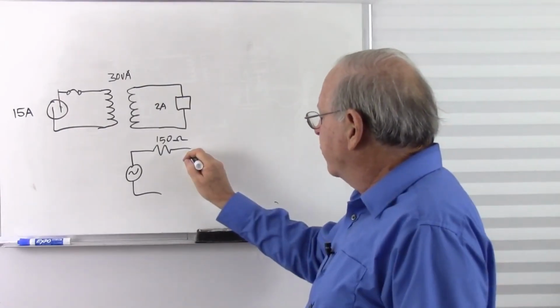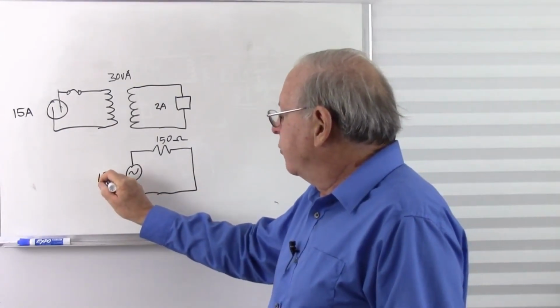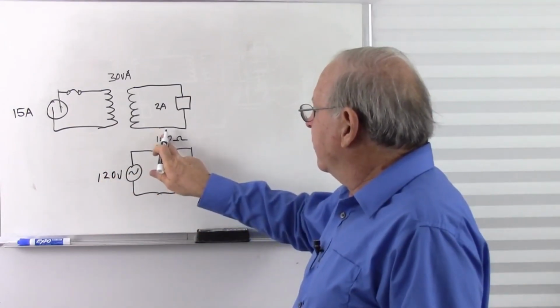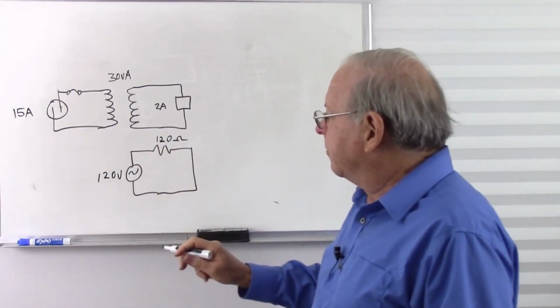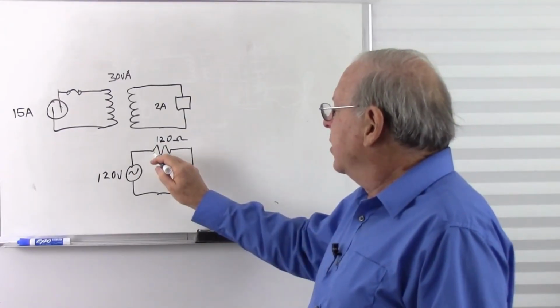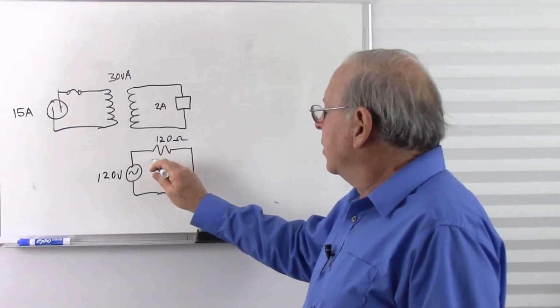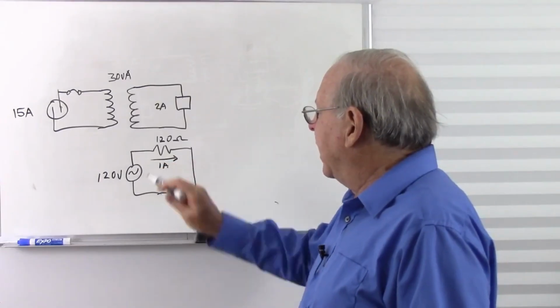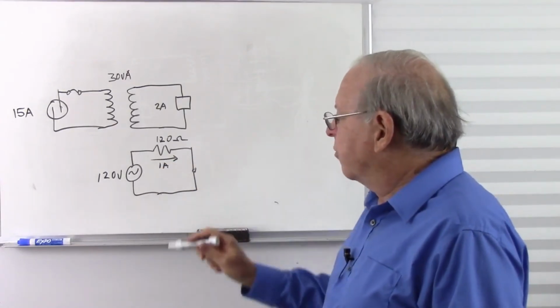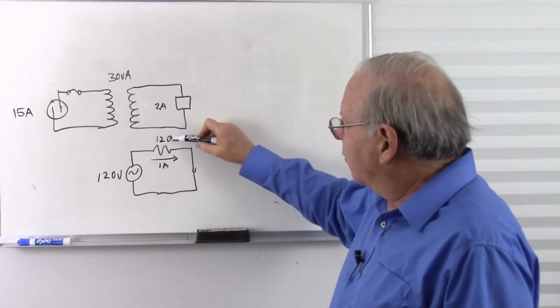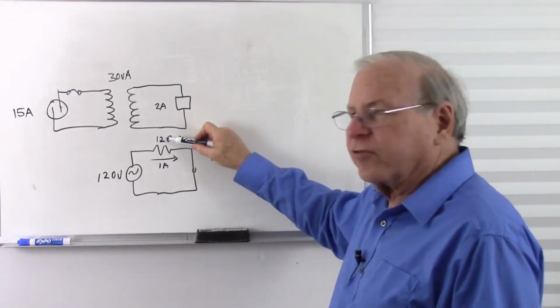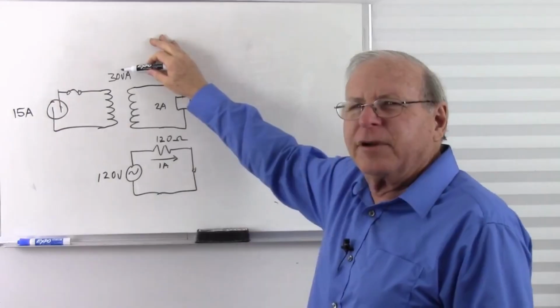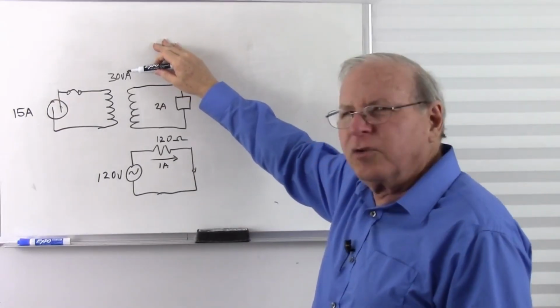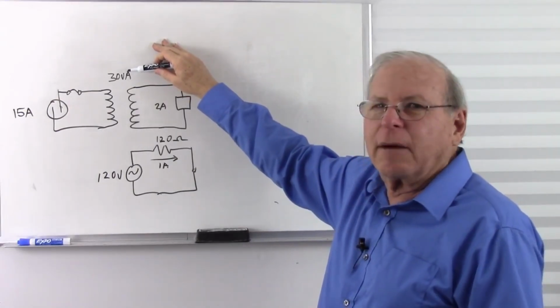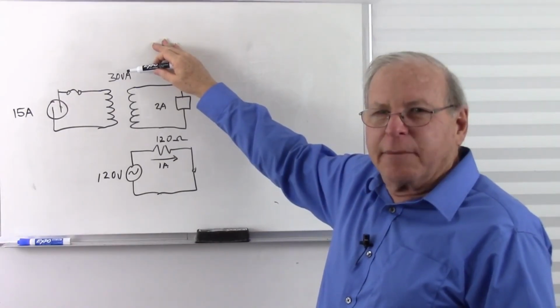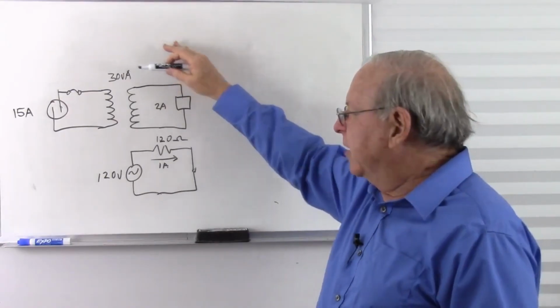And of course, if I put a short circuit over here, if this is 120 volts, let's make this 120 ohms just so I don't have to do any math in my head. 120 volts, 120 ohms, that's going to give me a total of 1 amp of current. So even if this is a short circuit, I'm only going to get 1 amp. So I think I have that wrong. I think it's probably about half the resistance of what I said before. I think a 30 volt amp transformer can give you about 2 amps max, just off the top of my head. Probably rated at half an amp nominally, but might give you 2 amps max.